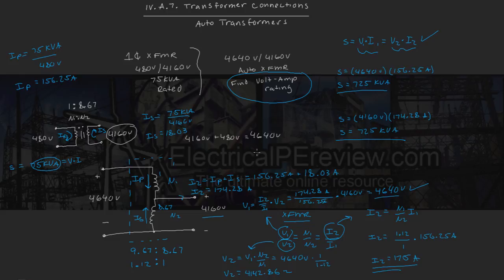The interesting thing to point out is if we compare our previous power rating of 75 kVA on our single phase transformer to our new configuration, we've got a massive 725 kVA rating. Now you might think, where does that tremendous increase in power rating come from? We're going to be able to step down 4640 volts to 4160, a lot more power, because we're only coming up with a difference of 480 volts from our input to our output, compared to up here, when we're stepping up from 480 to 4160, or stepping down from 4160 to 480, that's a much bigger gap in voltage, so we're not going to be able to transform nearly as much power with that configuration.